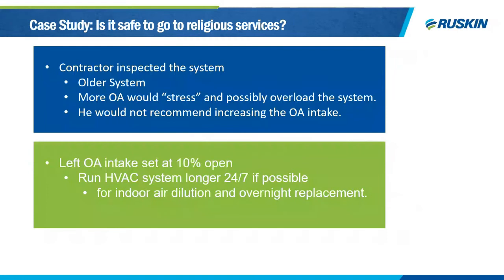The contractor came in, he looked at it, says, yeah, it's an older system. I think more outside air would stress, probably overload the system. The HVAC contractor recommended the outside air intake be left at its current setting of 10% open. What caught my ear during this conversation is what the contractor said, quote, the outside air damper set to 10%. Are they operating under the assumption that 10% open equals 10% outside air? It doesn't work that way, but this is a common misconception.